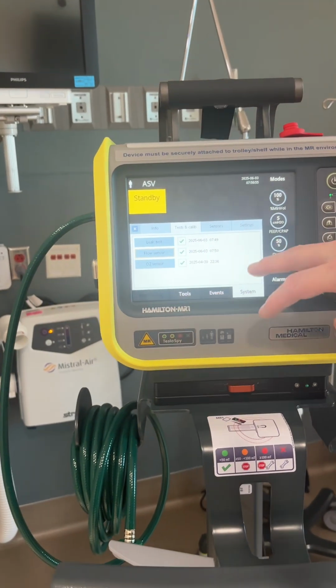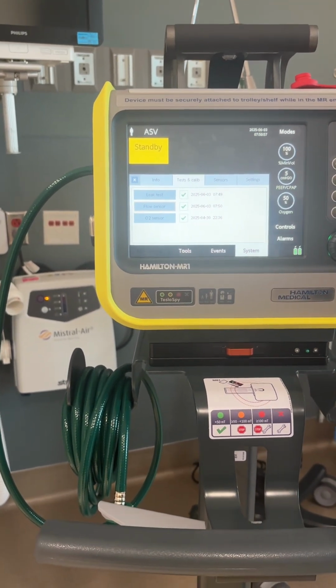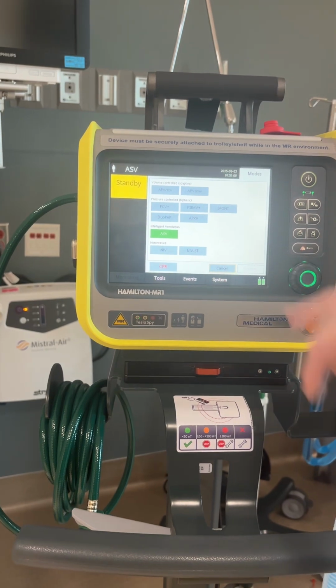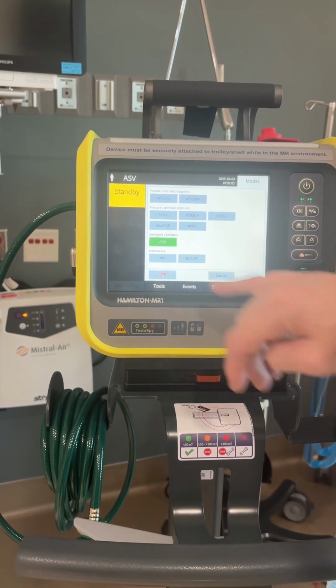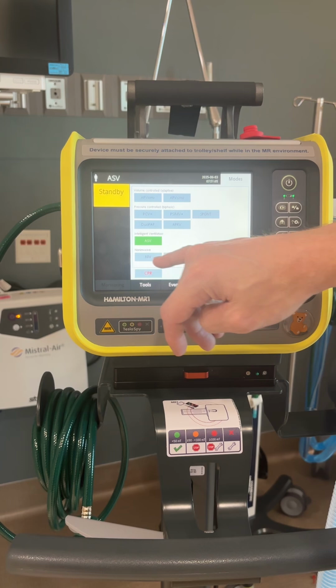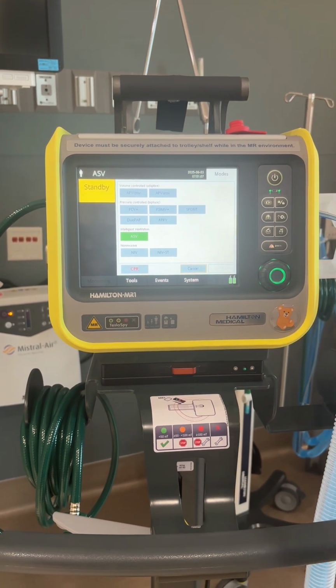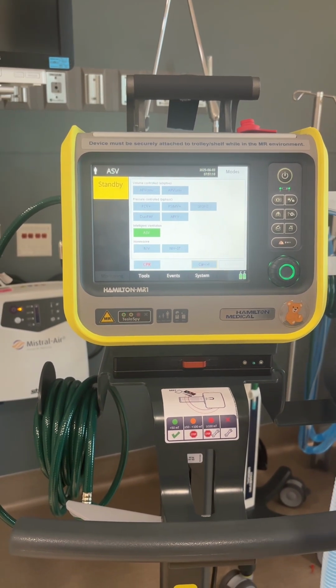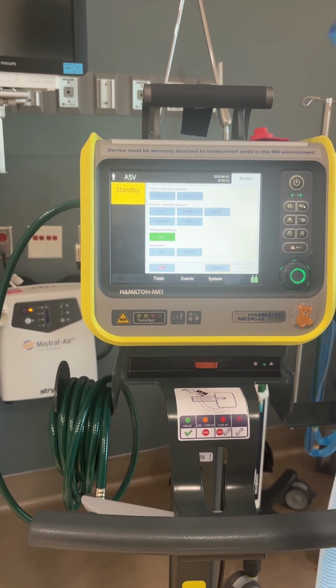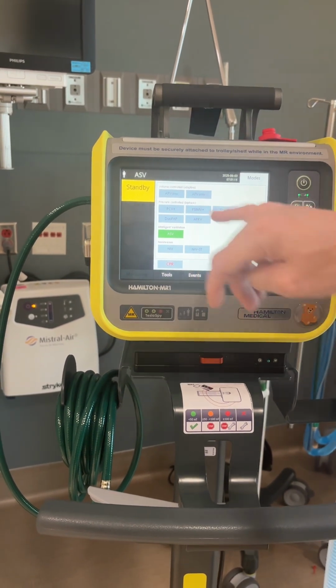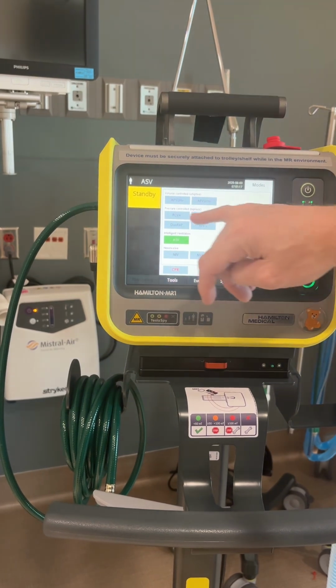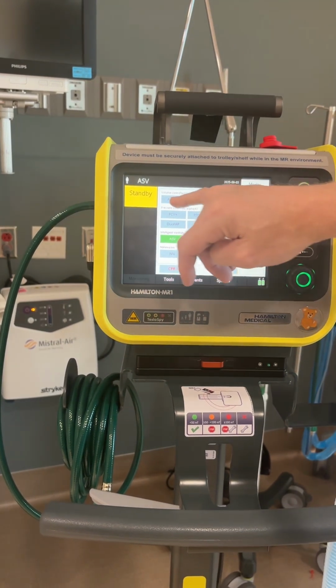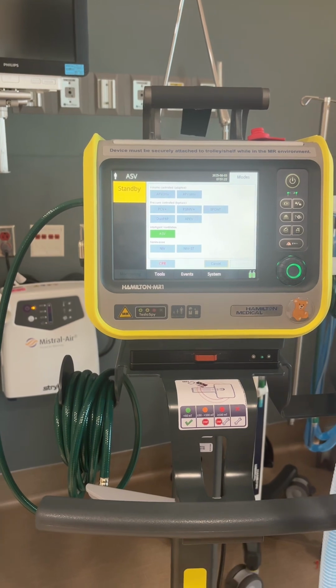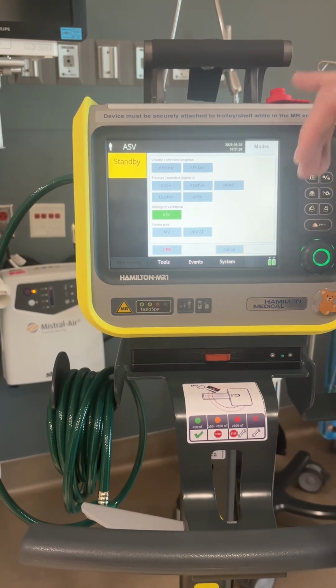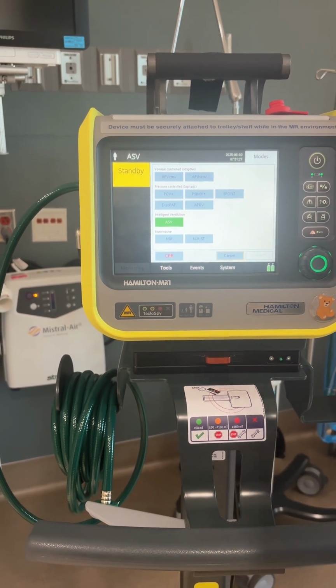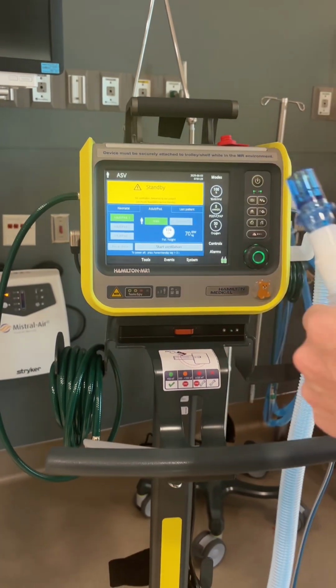If you need to do the O2 sensor, you can do the O2 sensor, or you can go straight to your modes. You can do whatever mode you need. If you wanted to do a BiPAP, you would do NIV, NIV-ST. Our BiPAP masks, I did find out, are MRI compatible, so we can use them on the MRI. But the main settings you're going to be using are the volume control modes right here, and then you've got your dual PAP. But we'll go through modes later in a different video. But that's really the setup for that.